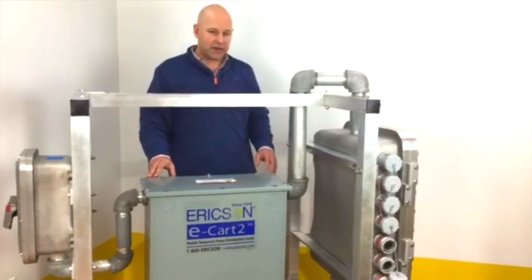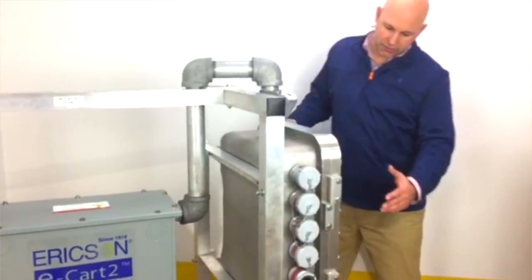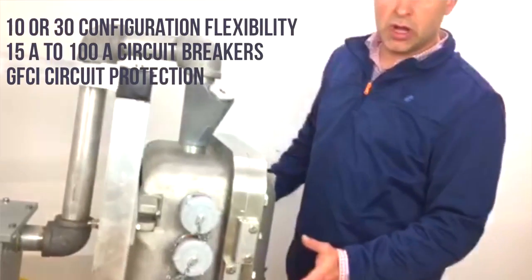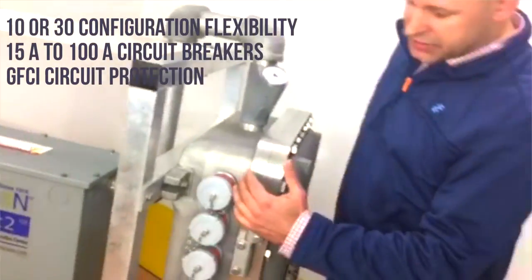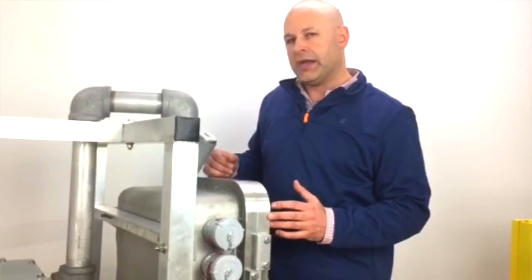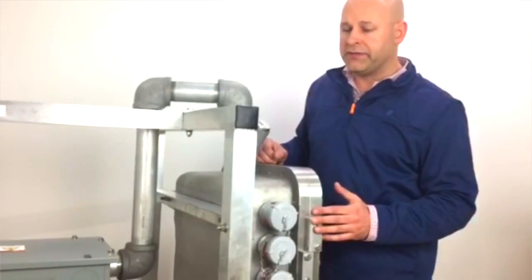Going down to the distribution side of this E-Cart II platform, we have our distribution enclosure. This unit is 18 circuits, but also comes in a smaller enclosure — from 6 circuits to 10 to 12 and up to 18. On this enclosure, we drilled and tapped 18 NEMA 5-20 receptacles with twist caps. These also provide a NEMA 3R fitting, so this unit is rated for outdoor use with a NEMA 3R and Class 1-2 rating.